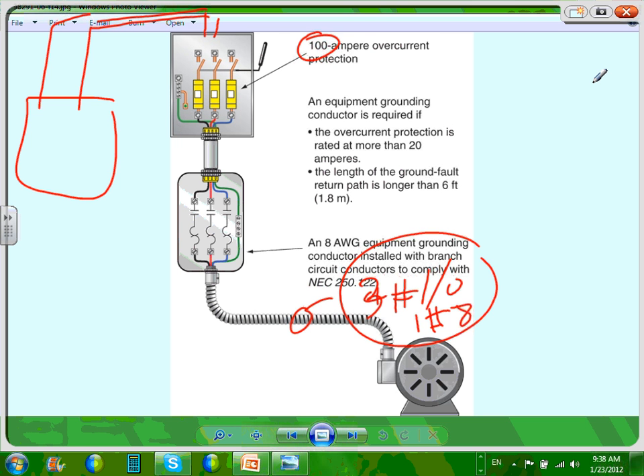Here, does the flex need to be grounded? Yes, the flex has to be grounded. So you have to have a special type of connector. Big deal, guys, if you're going to get confused about what type of connector goes with what type of fixture. There's a lot. So yes, the connector here and the connector here have to be rated for the flex, and they ground the flex. So in reality, you're going to have 2 grounds: 1 ground going through the green wire and 1 ground going through the flex shield.